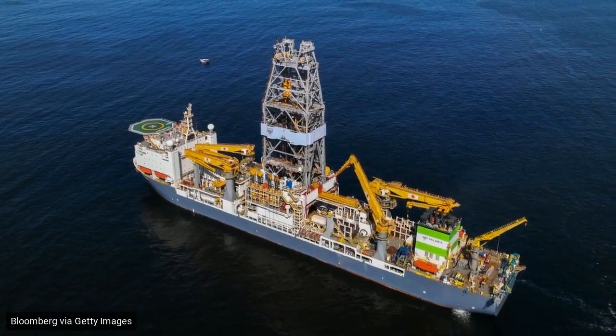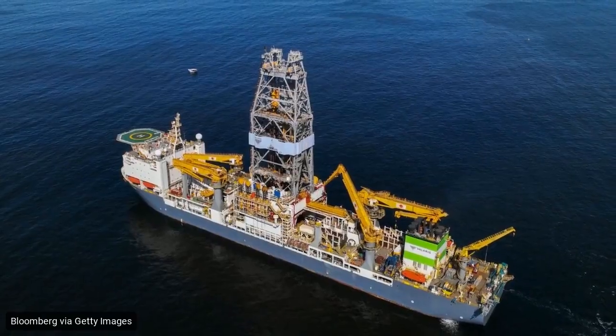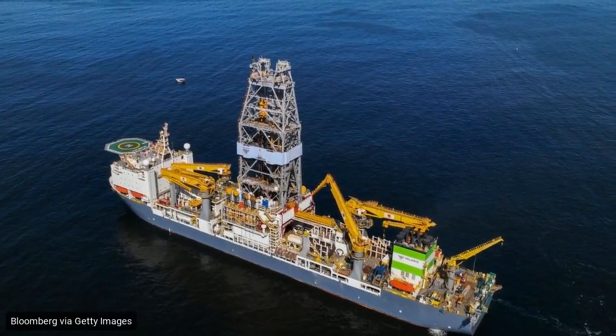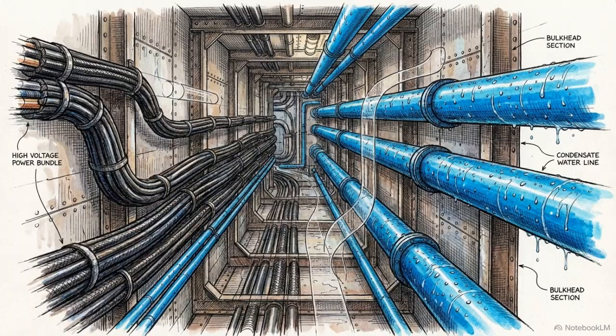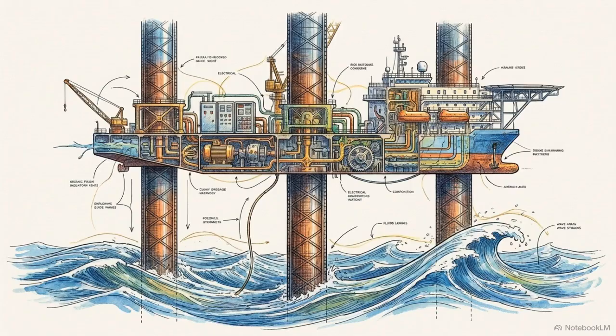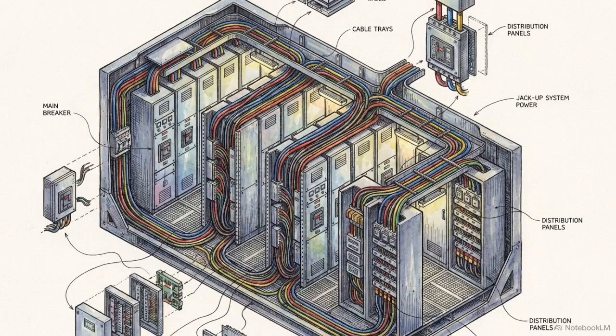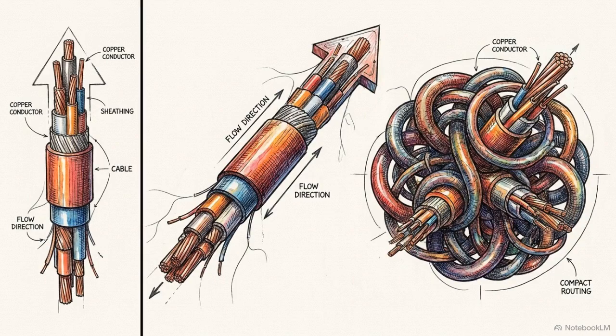A drill ship uses a fore-to-aft layout. Power must travel the entire length of the ship to reach the derrick, requiring exceptionally long cable runs that introduce voltage drops and demand water-cooled drives to survive the salt air. A jack-up rig stands on the seabed with its hull elevated out of the water. Because the hull area is small, switch rooms are densely packed, which creates a compact footprint but leaves little room for maintenance. These comparisons illustrate topological determinism, the reality that the vessel's physical hull dictates the internal electrical architecture.